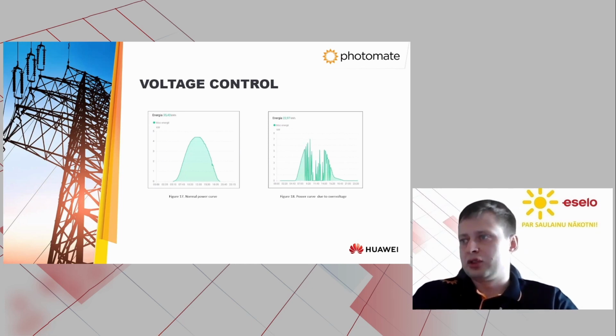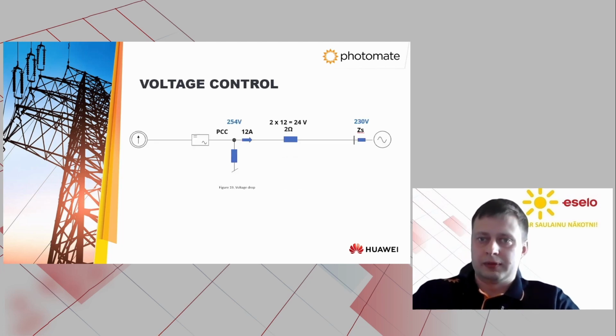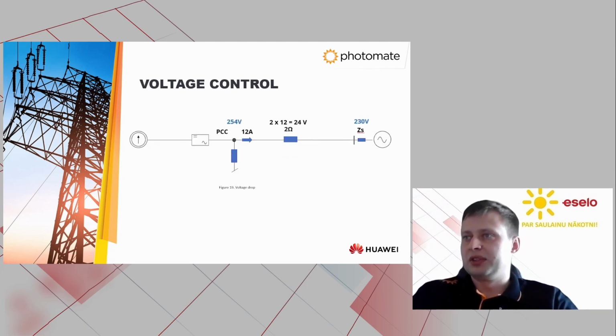this problem, as shown in figure 18. During the day, the inverter is disconnecting and connecting again, disconnecting and connecting again, but there are no problems in the morning and the evening. The primary cause of this disconnection of the inverter from the grid during the day is commonly associated with overvoltage.